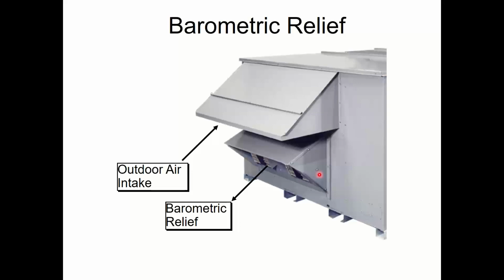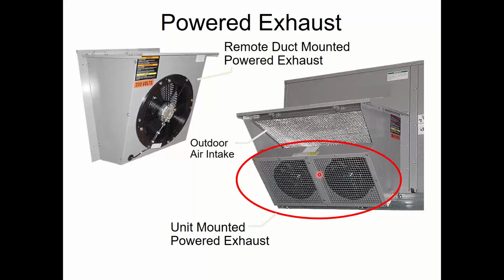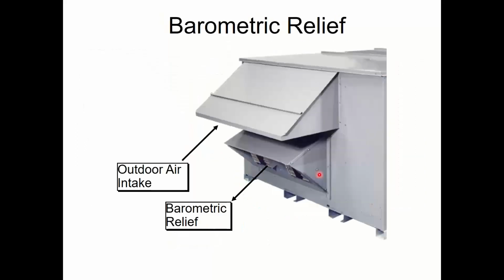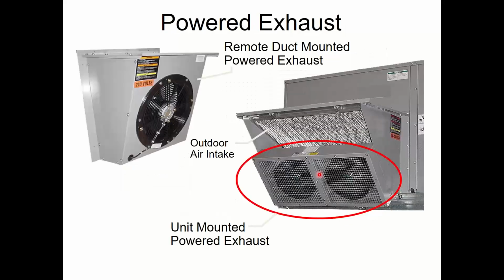If the system gets big, and by big I mean the ductwork gets long and restrictive, then the air in the room that has that pressure says, I can either go out that 145 feet of duct to get to that barometric damper Ryan put in, or I can go 13 feet to that front door. Air is lazy. Path of least resistance. It goes to the front door. So if my return ductwork gets long and restrictive, instead of having a barometric relief, I'm going to put a power exhaust fan in there and suck the air out of the room. So I'm going to have a fan sucking air in, and a fan sucking air out of the building. And the more I open the damper, the more I'd like to turn that fan on.